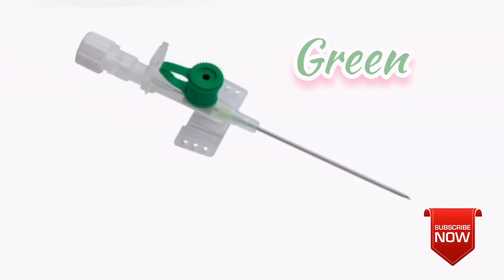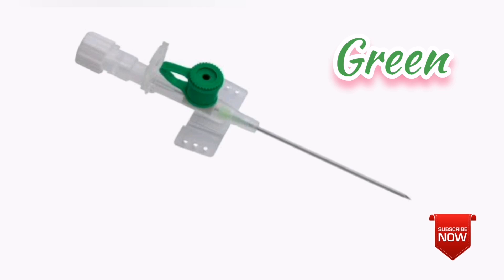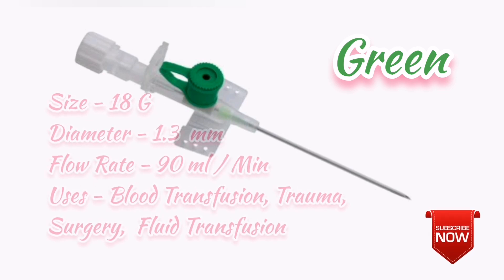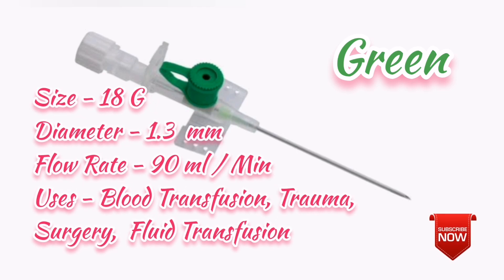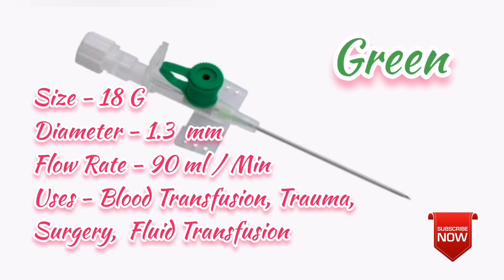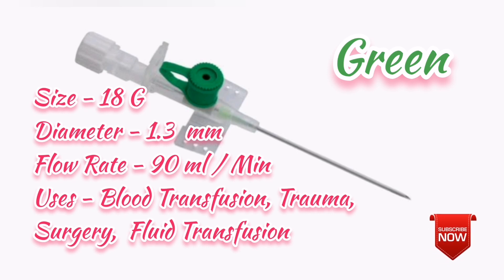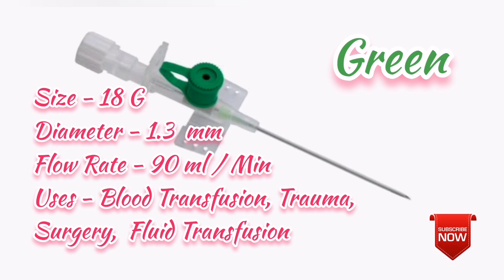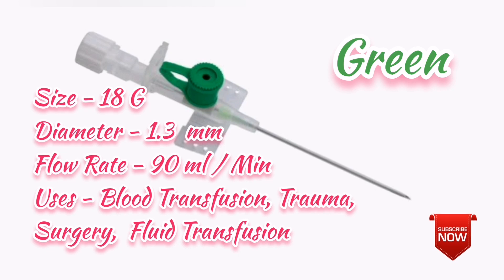The next color is green. The size is 18G. The diameter is 1.3 mm. The flow rate is 90 ml per minute. The use of this is normal blood transfusion, normal IV transfusion, medicine or IV infusion. It is commonly used in the adult group.